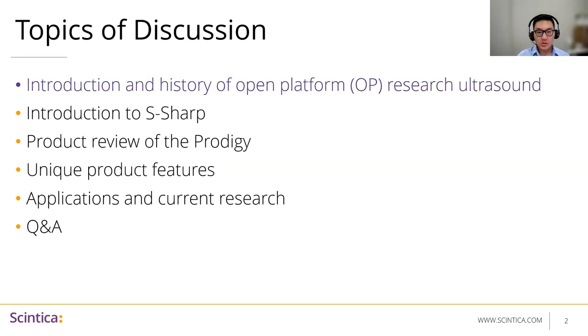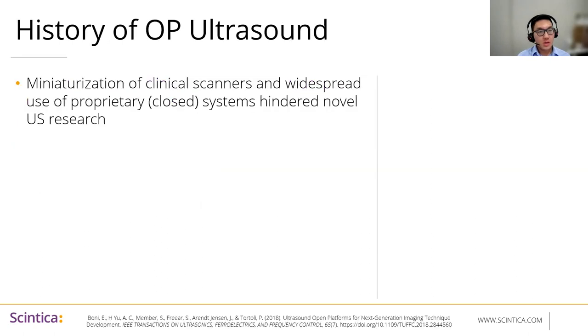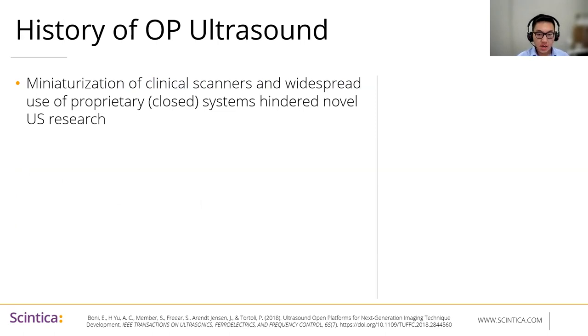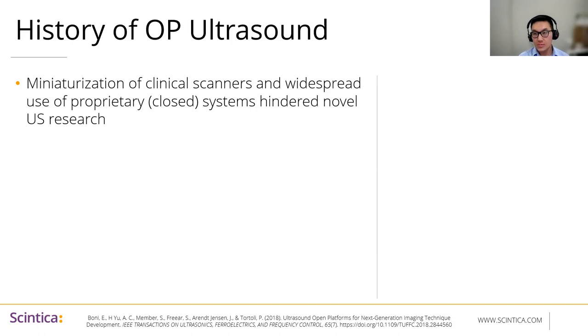Starting with open platform research ultrasound, it really goes back quite a few decades to when miniaturization of clinical scanners and widespread use of proprietary or closed systems began. This in a sense also hindered novel ultrasound research, as research groups could no longer easily access the raw data being generated. They were also potentially not able to change the transmit waveforms, adjust the pulses, or modify the sequences being transmitted in order to investigate novel imaging.